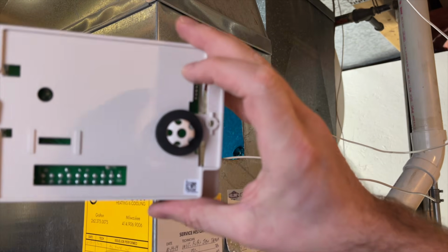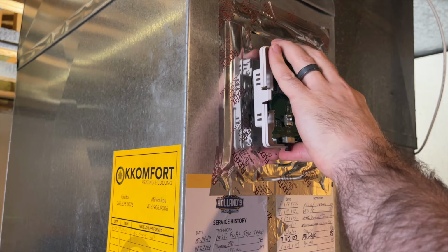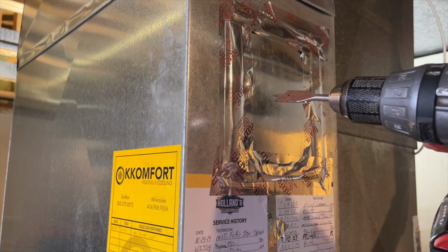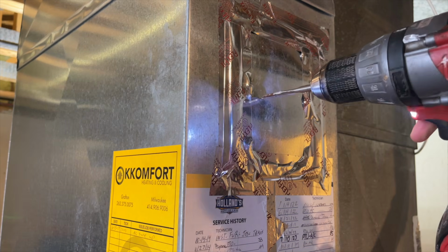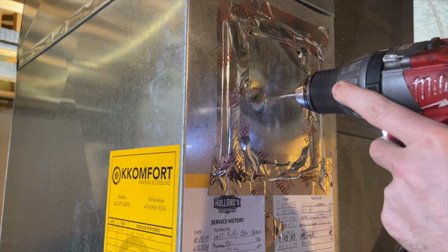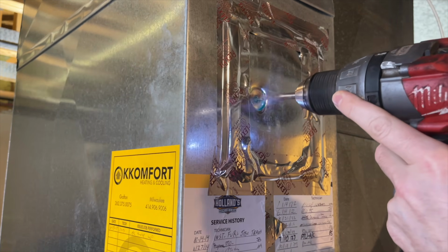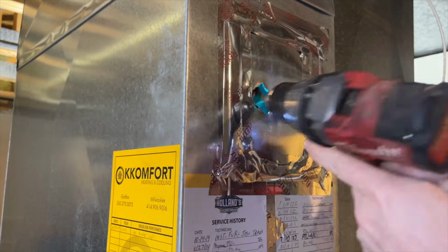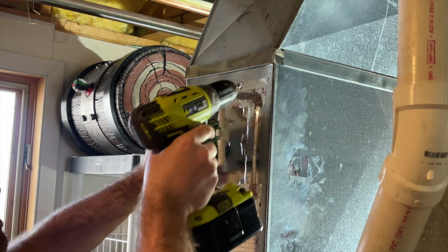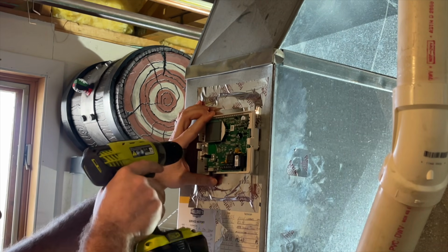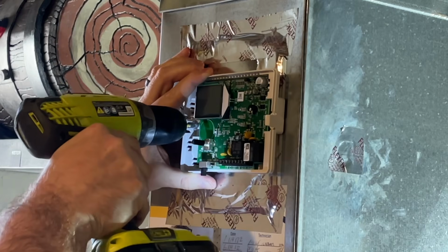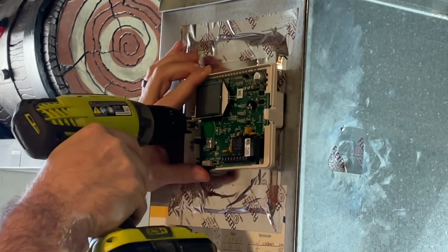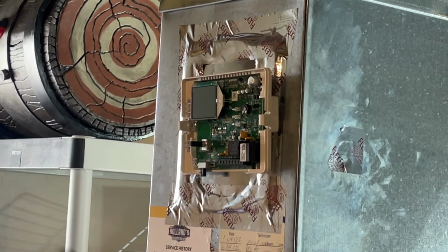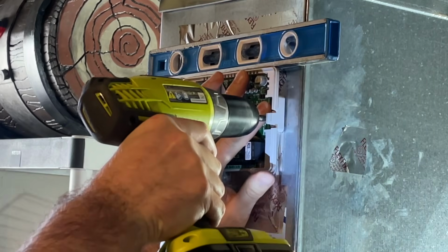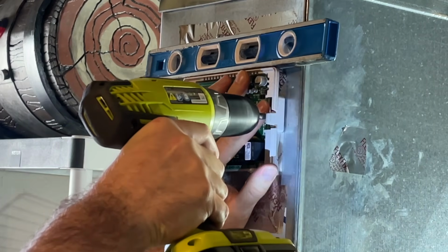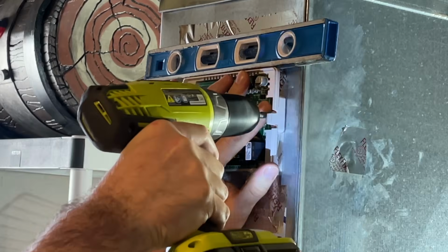The next installation is the humidistat. First, we need to cut a hole or drill a hole that will fit the sensor on the back of the humidistat, which is about 1 inch in diameter. I'm using a flat 1-inch drill bit to drill the hole, which I do not recommend. I would say use something with either teeth or cut a small hole and use the metal shears to cut your 1-inch hole out. Insert the sensor into the hole and secure the left side, which has a singular hole. The right side, however, has an elongated hole, which can be used to adjust the level of the humidistat.